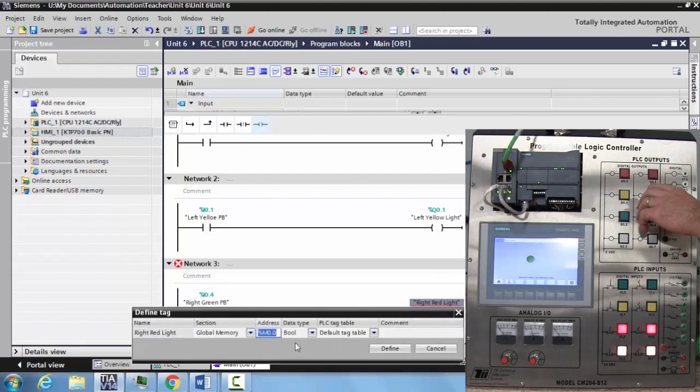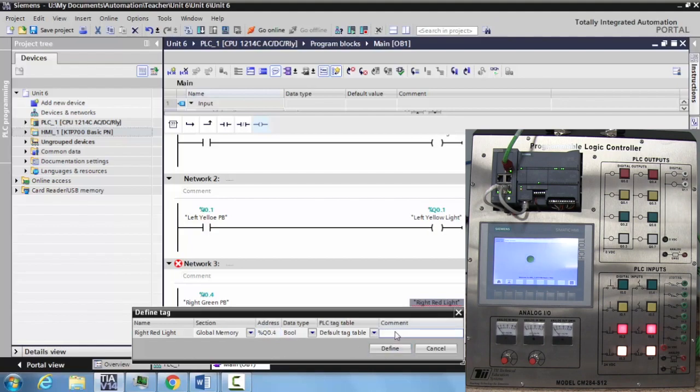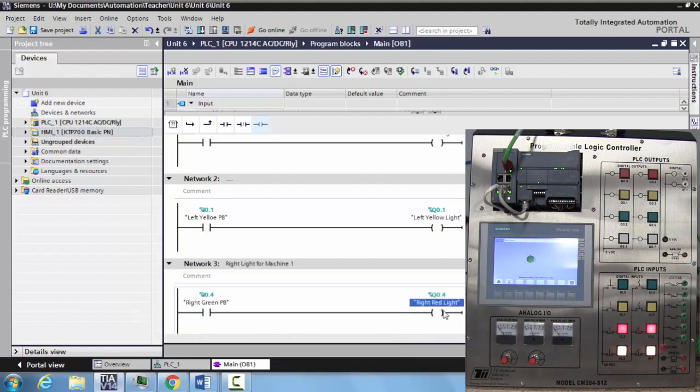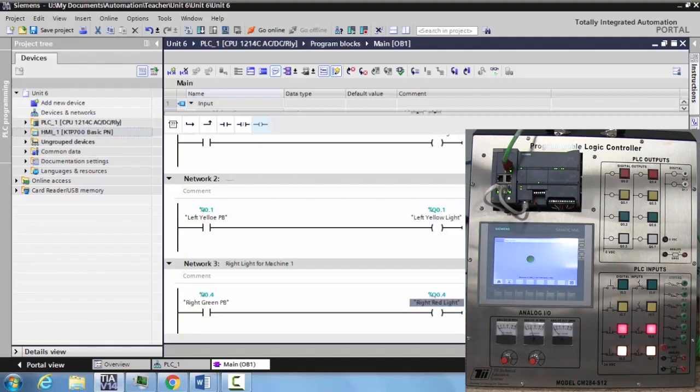We want to define this tag. Now this is Q zero dot four. So we come here and type Q zero dot four. If I wanted to add a comment in here, I could say right light for machine one. There it is. Hit define, and it's right here. If you hold over it, you can actually see that description, the comment we created. So this is another way of defining the tags as you're programming.